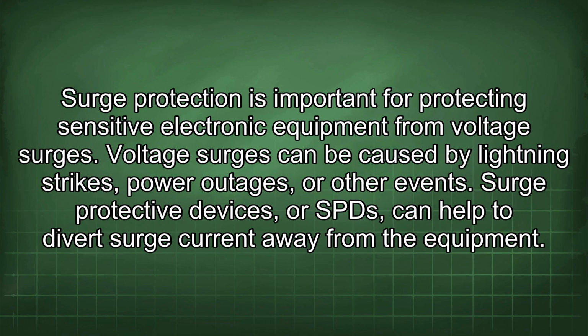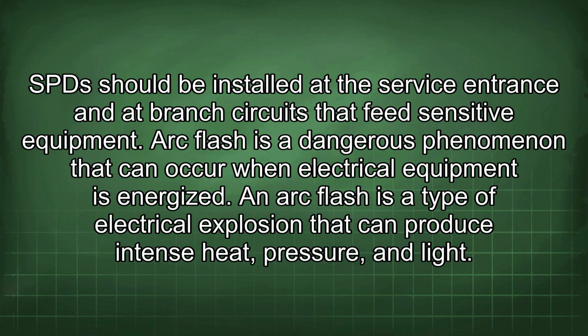Surge protection is important for protecting sensitive electronic equipment from voltage surges. Voltage surges can be caused by lightning strikes, power outages, or other events. Surge protective devices, or SPDs, can help to divert surge current away from the equipment. SPDs should be installed at the service entrance and at branch circuits that feed sensitive equipment.